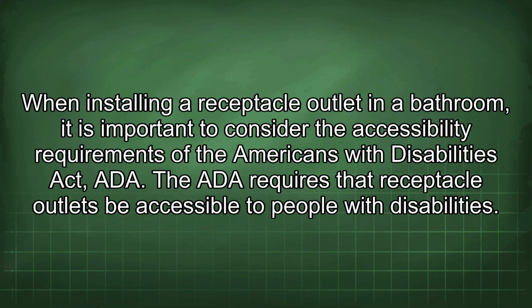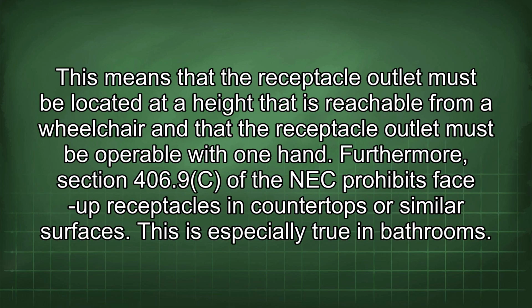When installing a receptacle outlet in a bathroom, it is important to consider the accessibility requirements of the Americans with Disabilities Act, ADA. The ADA requires that receptacle outlets be accessible to people with disabilities. This means that the receptacle outlet must be located at a height that is reachable from a wheelchair and that the receptacle outlet must be operable with one hand. Furthermore, Section 406.9c of the NEC prohibits face-up receptacles on countertops or similar surfaces. This is especially true in bathrooms.